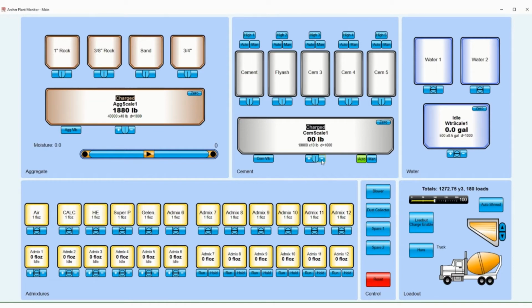If a scale is designed with two inching gates, you must click and hold the corresponding button to open or close the gates. Otherwise, a single click on the appropriate button is sufficient to start or stop the discharge. If a scale is configured with a vibrator and that scale reaches near empty, you can click and hold the open plus button to manually activate the vibrator.